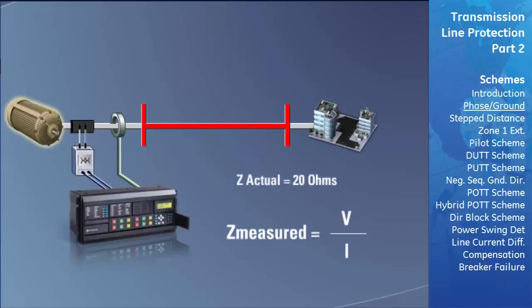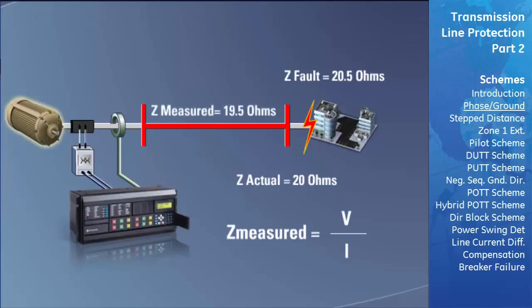For example, assume the actual impedance of our transmission line is 20 ohms and a fault occurs just past this line on the next adjacent circuit. The actual impedance from the relay's measurement point to this fault is 20.5 ohms. Due to inaccuracies in the CTs and VTs along with some transient effects, the relay may measure the impedance to the fault as less than it actually is, and see the fault as being on the line it is protecting, causing it to trip unnecessarily.